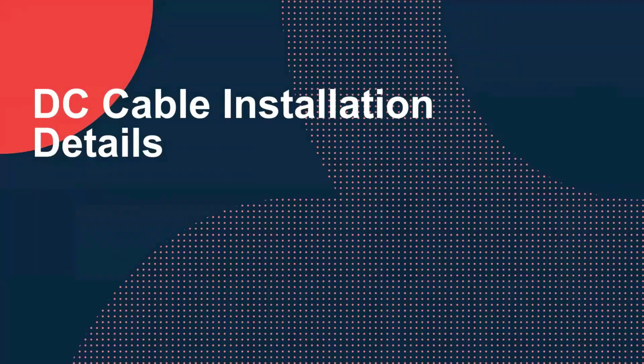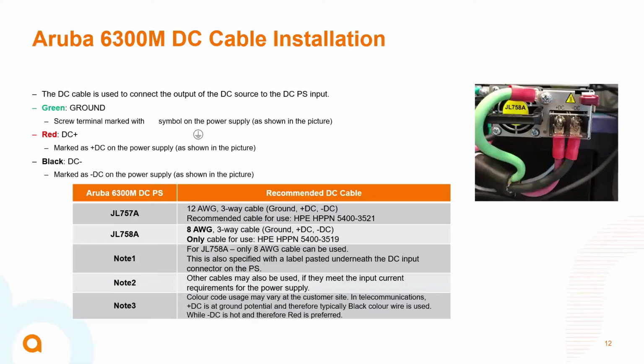Let's move on. This is again, as I told you, installation of the DC power cable is very, very important. With an AC power cable, what are you going to do? There is only one notch on the cable. You are going to insert it, either high line or low line, and plug it in, right? But in the case of a DC power supply, a little bit of electrical work is required, and it needs to happen very carefully.